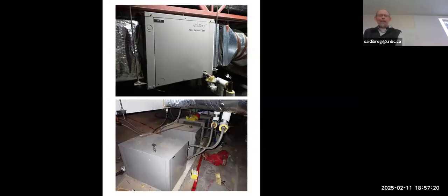Then that building loop runs up here into the glycol to air heat exchanger, which has a blower in it and blows air through, warming it in the winter and cooling it in the summer. And although these are aging and use refrigerant R22, and a lot of them were on their last legs when we were there, it's a well-designed system, and it uses only electricity as the energy source. And it's extremely efficient because of the thermodynamics of ground source heat transfer.